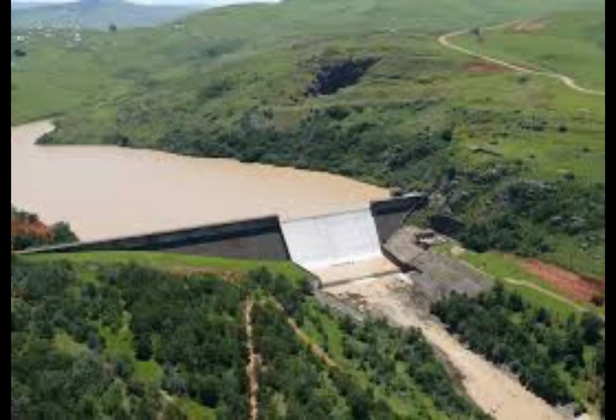3. Colley Wobbles Power Station. The Colley Wobbles Power Station is a hydroelectric power facility located approximately 30 kilometers east of Dutywa in the Amathole District municipality of the Eastern Cape of South Africa. Water is drawn from behind a dam on the Mbashe River and diverted through a penstock to the Colley Wobbles Power Station. The power station discharges into the Mbashe River. The powerhouse houses 3 Boving Francis turbines, each driving a 14 megawatts, 11 kV synchronous generator to give a total station output of 42 megawatts. The power station has provision for the installation of a future 4th machine.